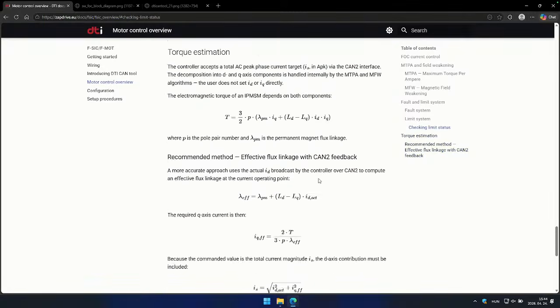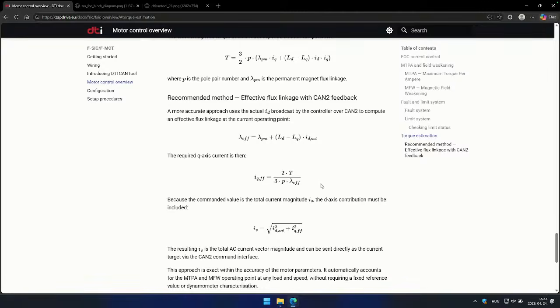If you would like very precise and accurate torque control, you have to do a dynamometer test, because this torque relation depends on Ld and Lq, which depend on the current. It also depends on lambda, the flux linkage, which is temperature dependent, and other factors can affect the torque you request. So do some testing with this method and make sure it produces the right torque for you.